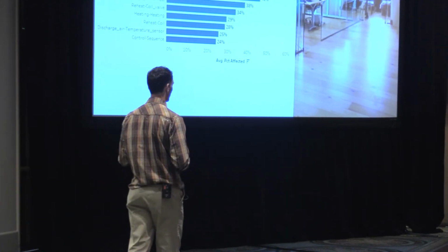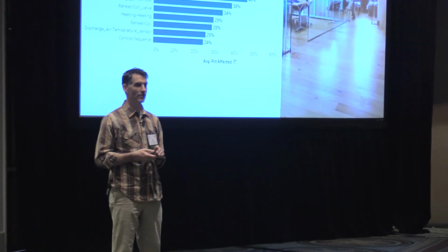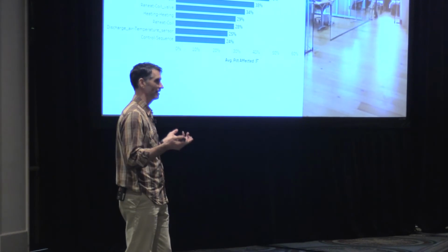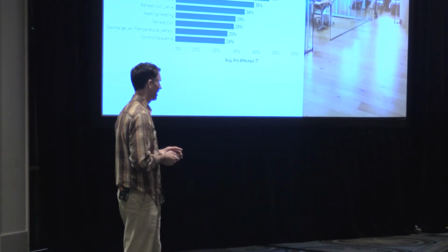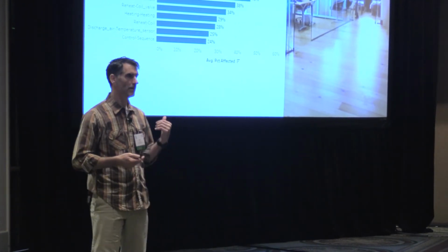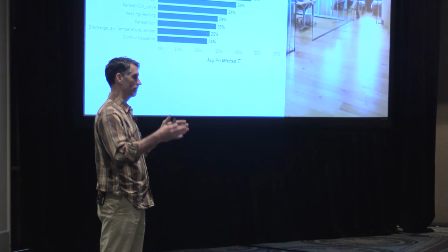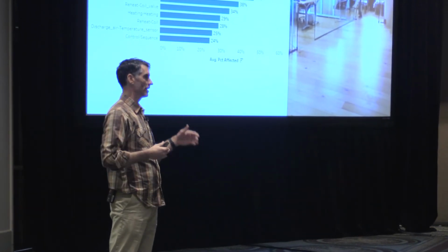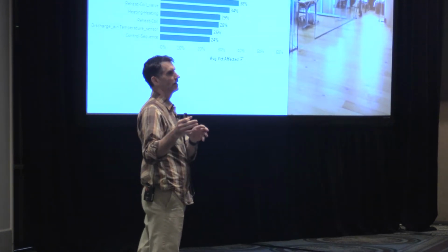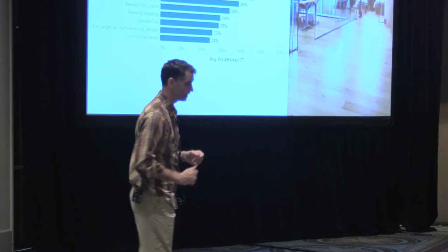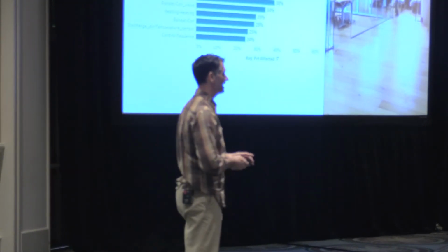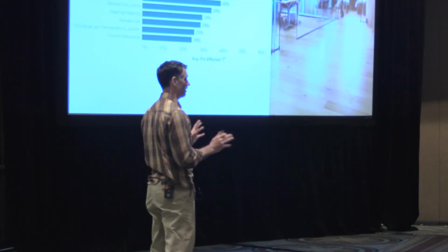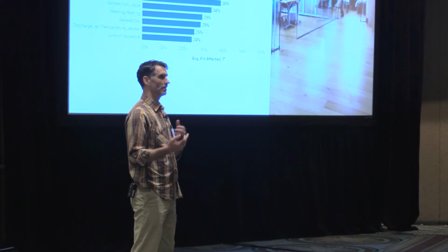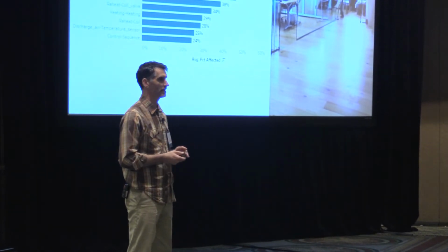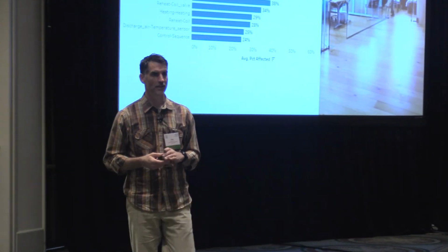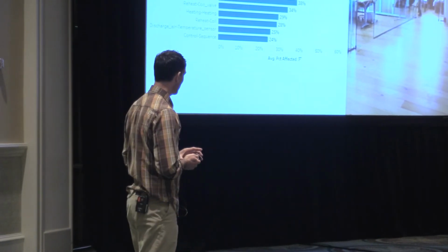I'll also mention the 80-20 principle here. You're probably familiar that in some buildings there are terminal units you just can't get quite right or balanced. Looking at both air handlers and terminal units, if you rank them by faults reported, the top third account for 80% of all faults—so it's not quite 80-20, more like 80-34%. Oddly, that holds true for both terminal units and air handlers: the top third of problematic units account for 80% of the faults.